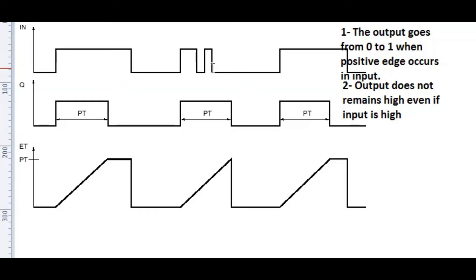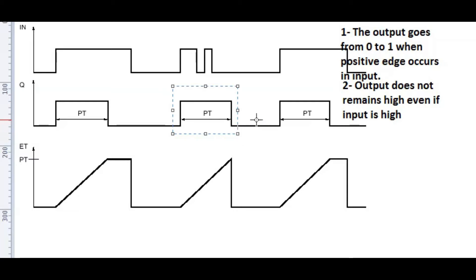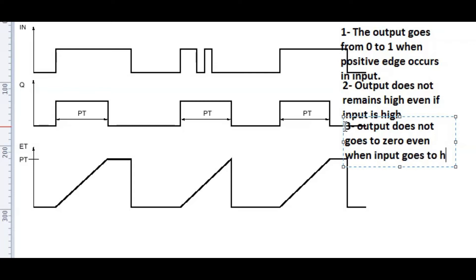Now let's see the third condition. As you can see from the graph, we give a positive edge and the output becomes high. But after some time — let's suppose after 2 seconds — we turn off the input. You can see that the output does not go to 0; it finishes its full timer of 10 seconds and then goes to 0. That means the third working principle of this timer is that the output does not go to 0 even when the input goes to 0.